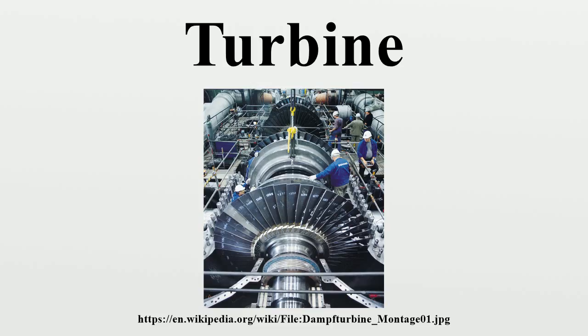The design is essentially a multi-stage radial turbine offering great efficiency, 4 times as large heat drop per stage as in the reaction turbine. Extremely compact design and the type met particular success in back-pressure power plants. However, contrary to other designs, large steam volumes are handled with difficulty and only a combination with axial flow turbines admits the turbine to be built for power greater than 50 megawatts.